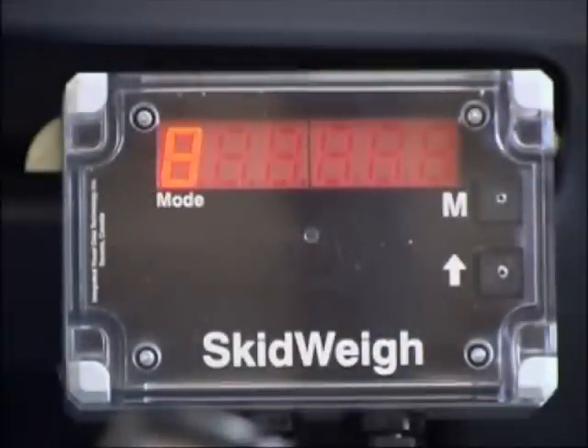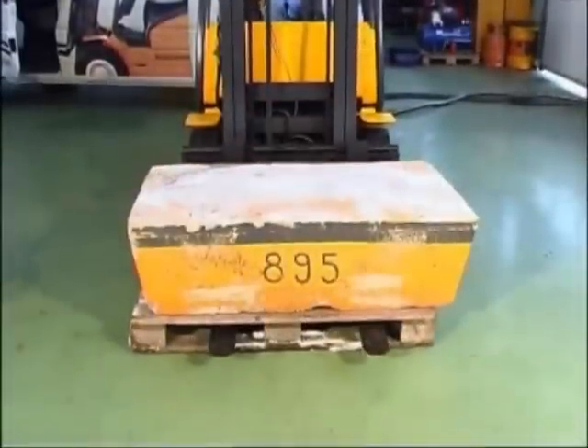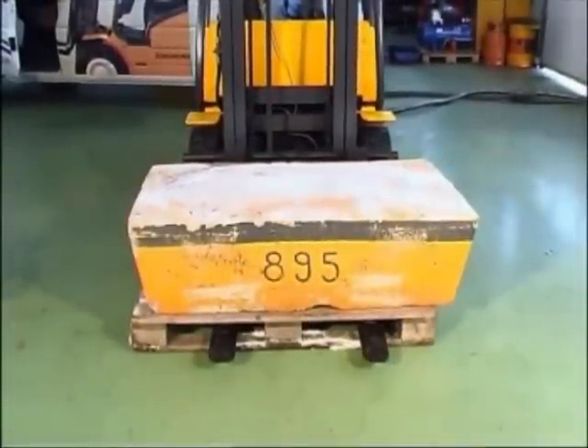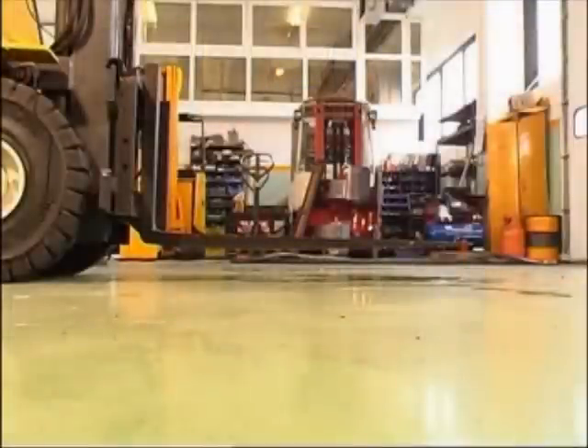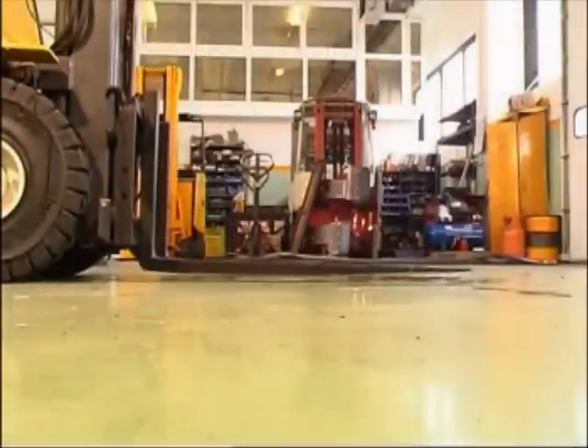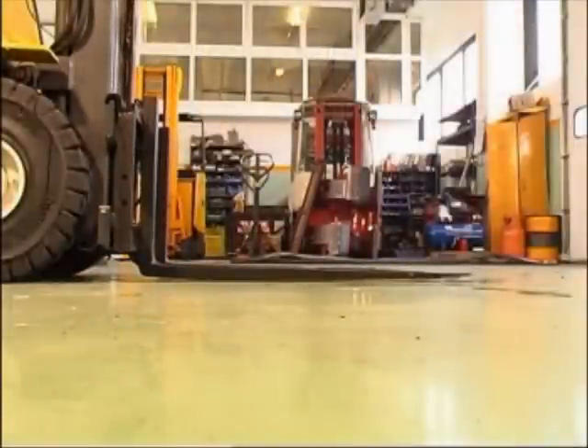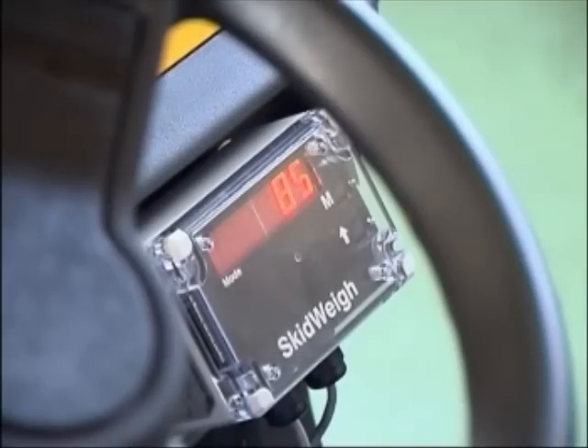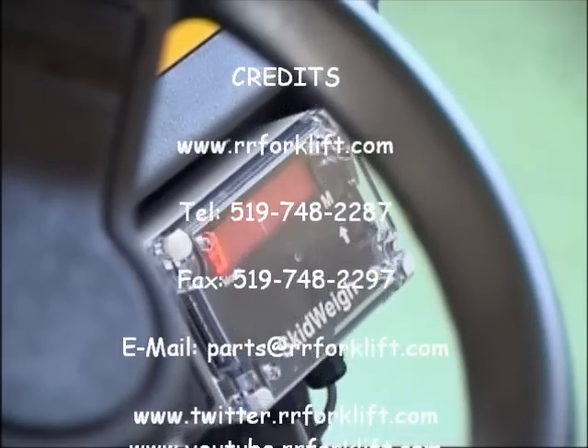There are only 2 buttons used to calibrate and set up the system, and these are M and arrow up. In the example on the video, we have a known calibration weight for a cement block of 895 kilograms. Lower the empty forks to the ground, turn the ignition switch on. The right side of the display shows the software version 85. This number will vary depending on the software version.